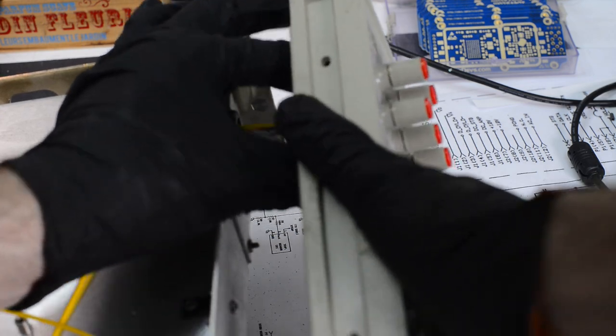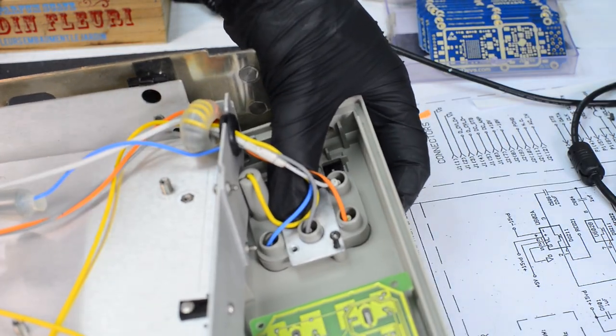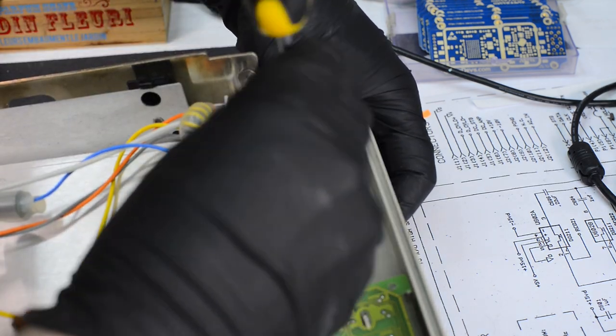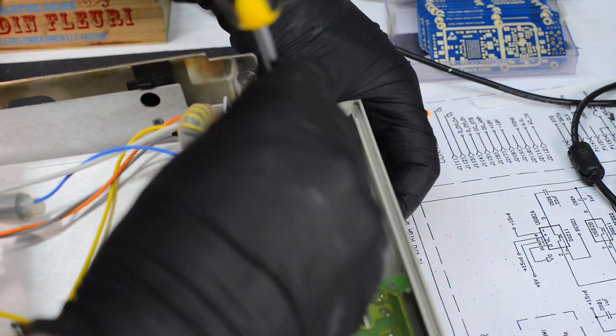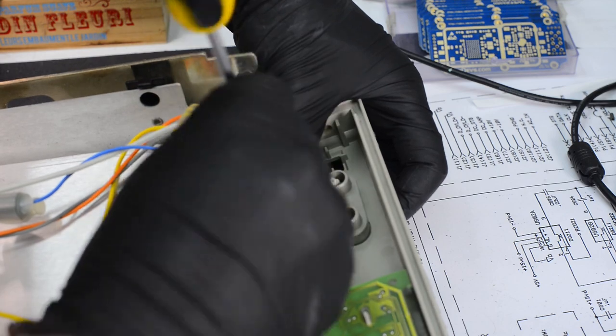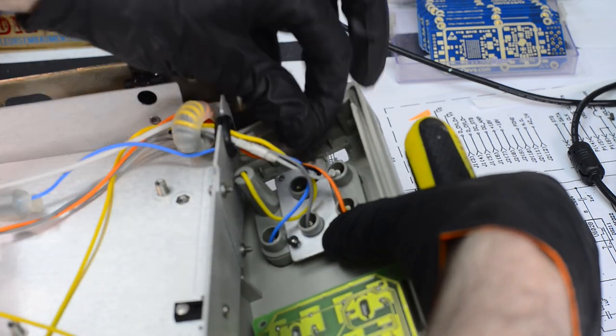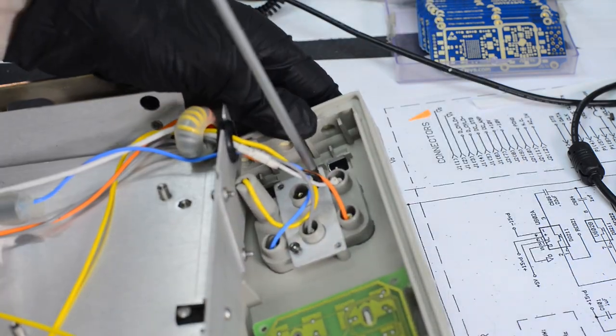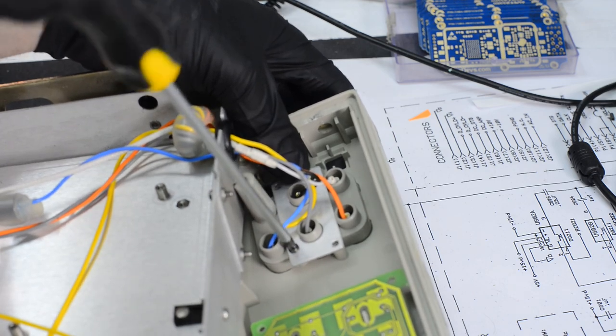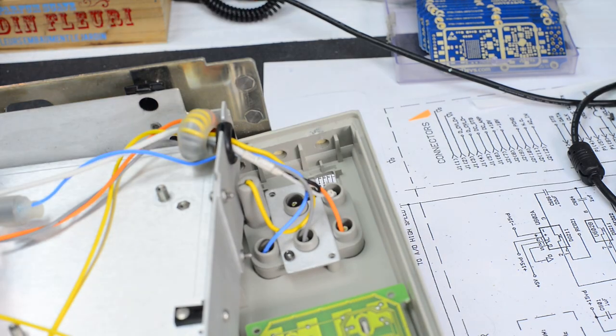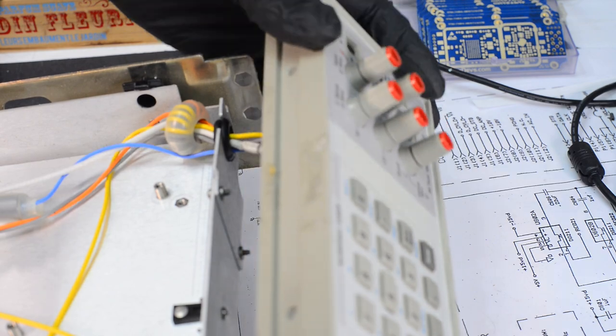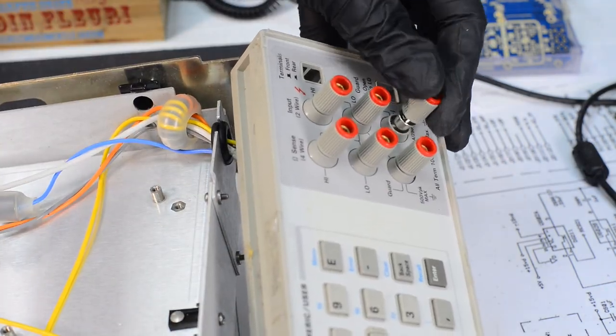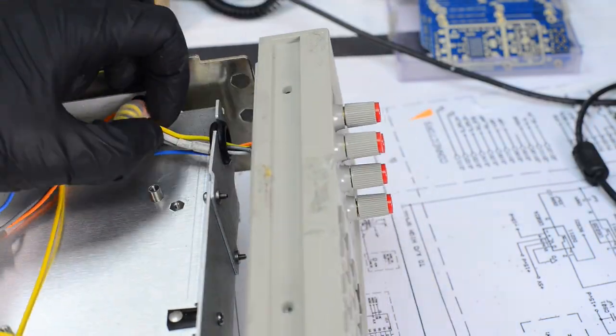The front plastic panel does not have any metal inserts, so it's just a self-tapping screw into a plastic standoff right there. You need to be careful not to over-tighten it and not to apply too much pressure to the block, otherwise you can break the fragile pin. So now we have everything installed and it looks good to go.